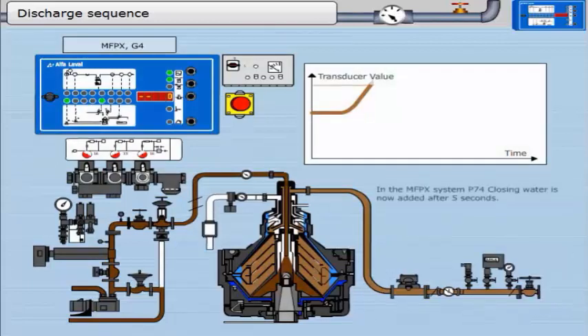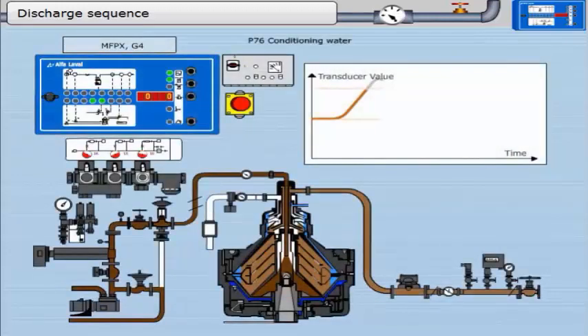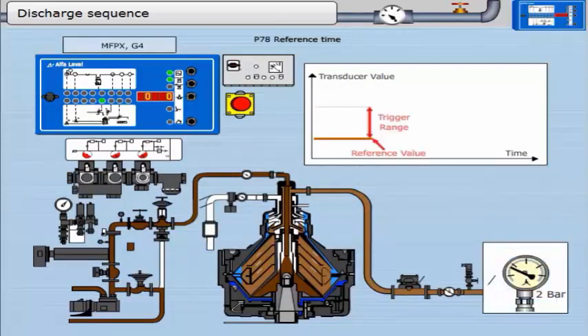In the MFPX system, P74 — closing water — is added after 5 seconds. Next we will show P76, conditioning water. A small amount of conditioning water is added to help with the next discharge; this timer runs for 25 seconds. The pressure gauge in the outlet should now recover to 2 bar when water is being added. The new stored reference value can be higher or lower than the previous reference. If at any time the actual value of the transducer moves below the stored reference, the reference moves and stays at this value. This timer runs for 30 seconds.